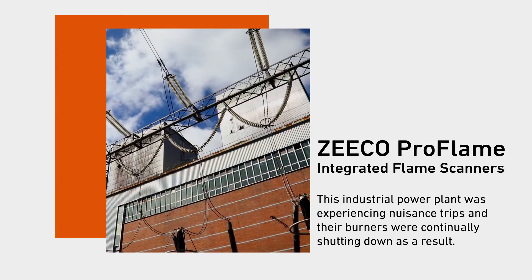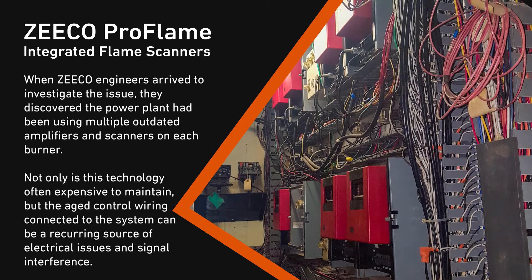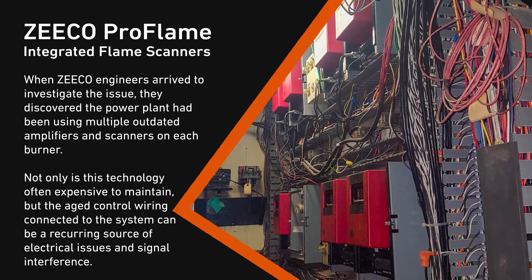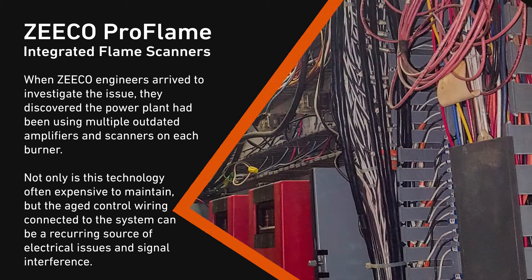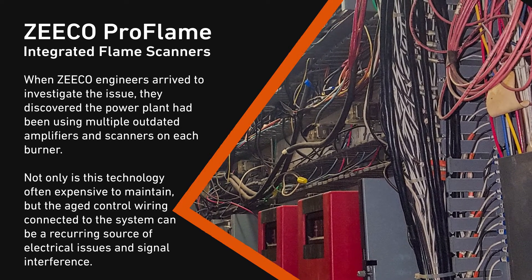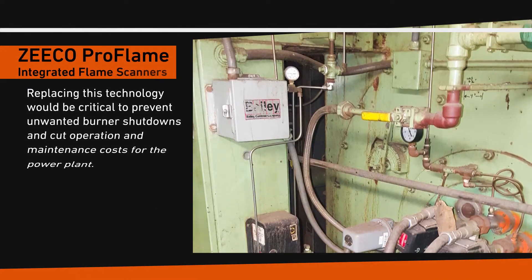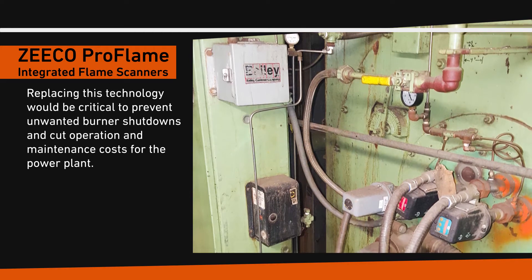This industrial power plant was experiencing nuisance trips and their burners were continually shutting down as a result. When ZEECO engineers arrived to investigate the issue, they discovered the power plant had been using multiple outdated amplifiers and scanners on each burner. Not only is this technology often expensive to maintain, but the aged control wiring connected to the system can be a recurring source of electrical issues and signal interference. Replacing this technology would be critical to prevent unwanted burner shutdowns and cut operation and maintenance costs for the power plant.